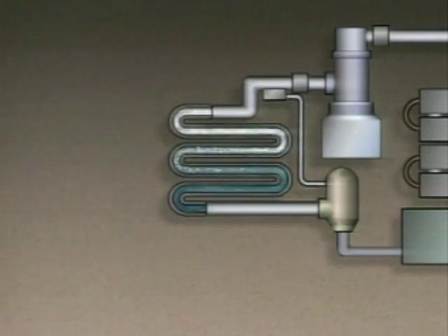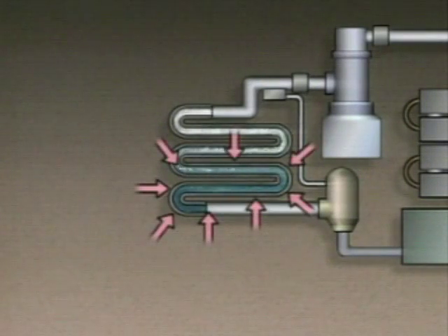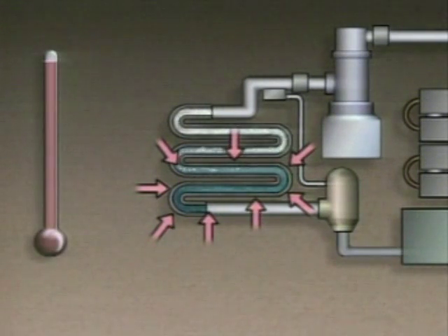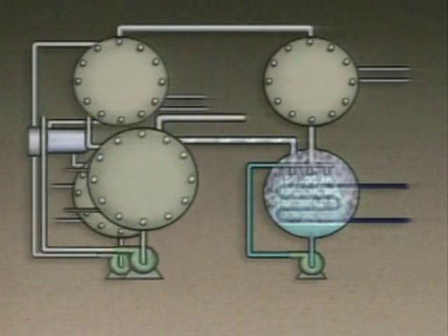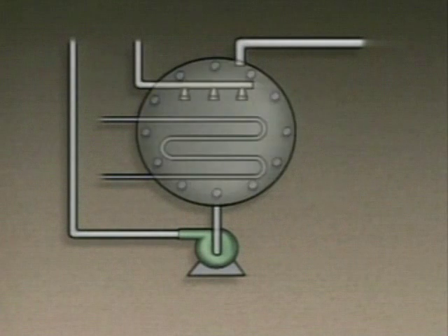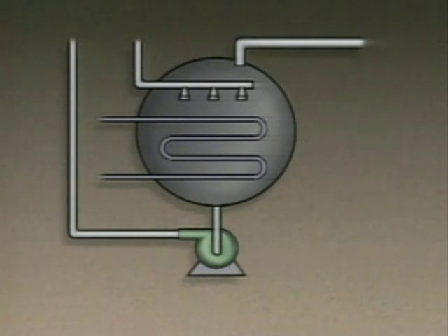Next, the refrigerant enters the evaporator, where it absorbs heat from the evaporator's surroundings and changes completely to a vapor. As the refrigerant absorbs heat, it cools the evaporator's surroundings. The low pressure in the system is achieved by using a chemical absorbent such as lithium bromide.